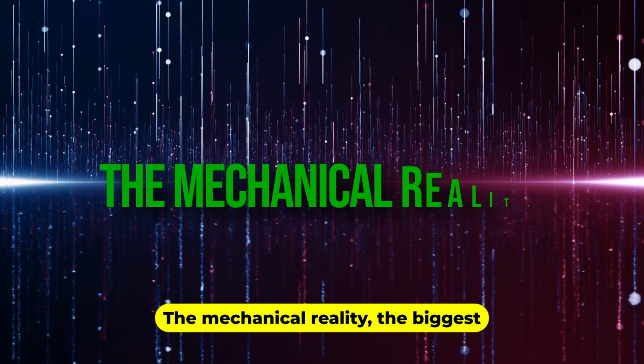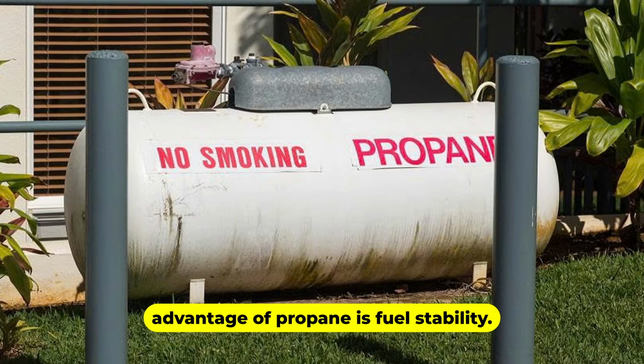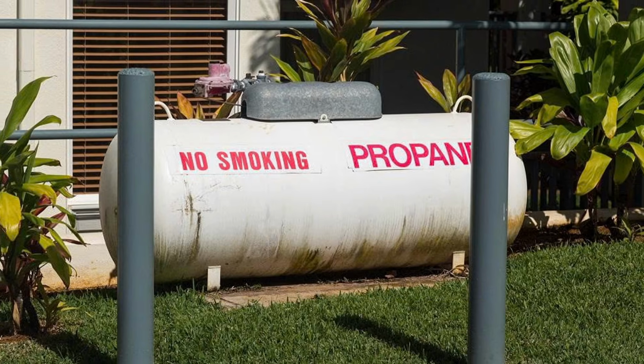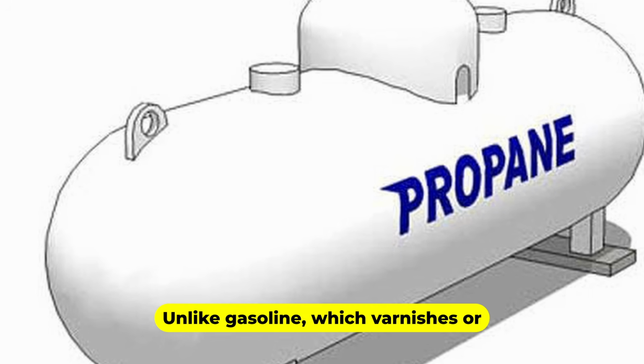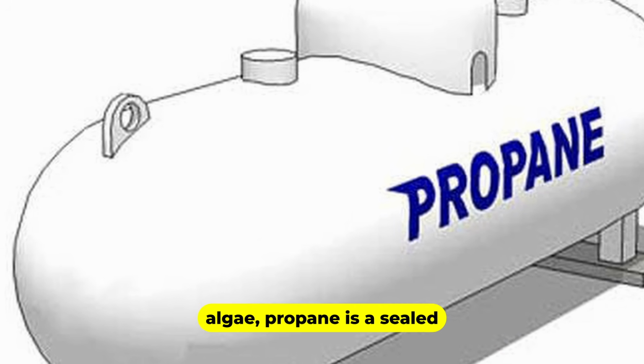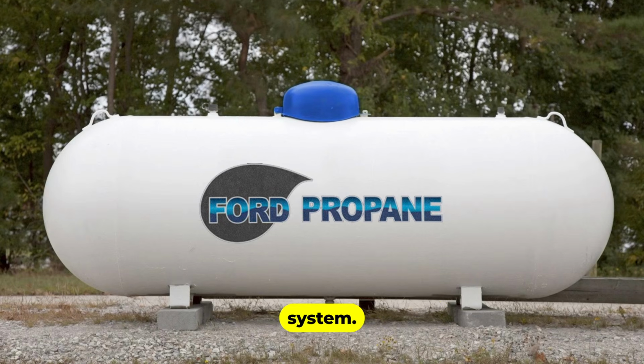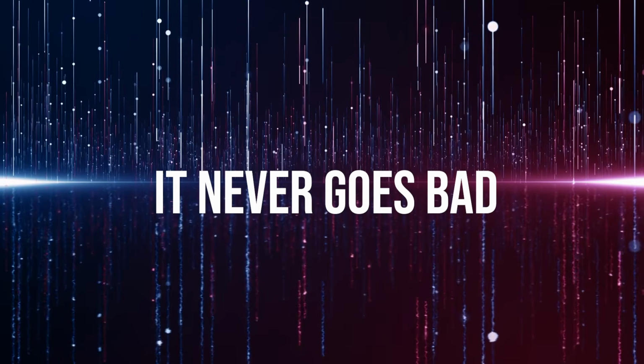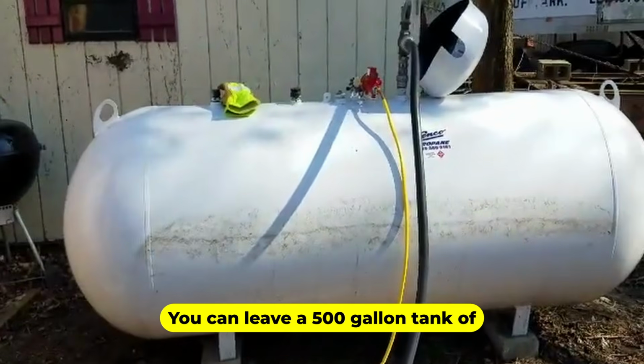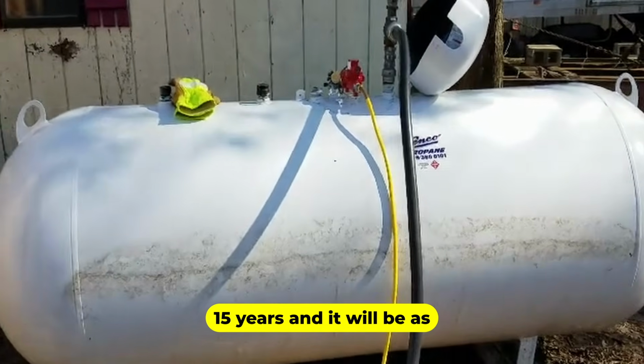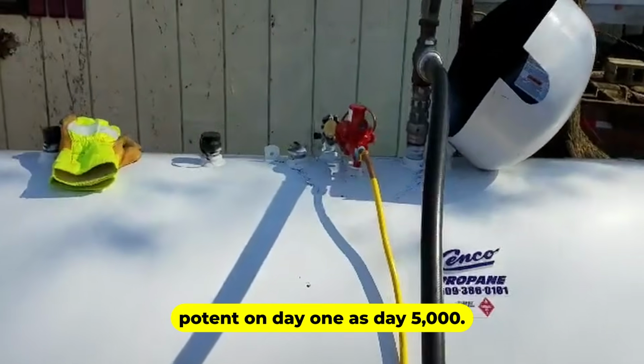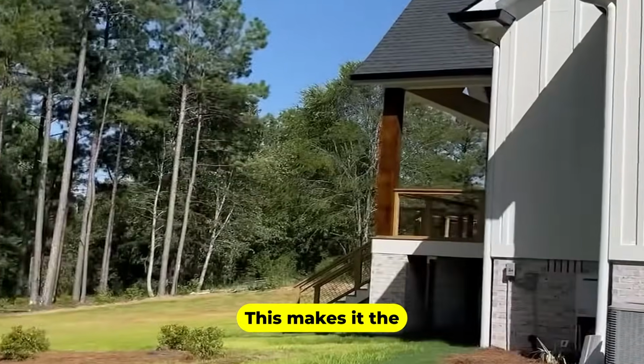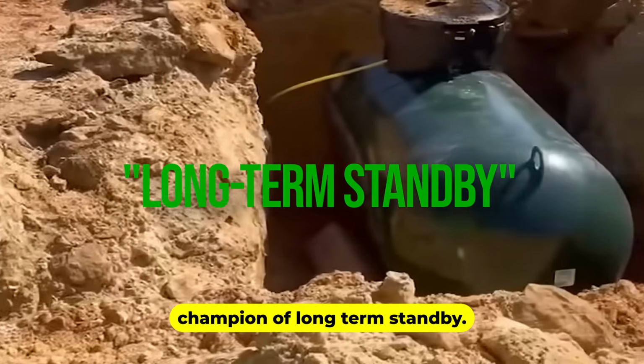The mechanical reality. The biggest advantage of propane is fuel stability. Unlike gasoline, which varnishes, or diesel, which can grow algae, propane is a sealed system. It never goes bad. You can leave a 500-gallon tank of propane in your yard for 15 years, and it will be as potent on day 1 as day 5,000. This makes it the champion of long-term standby.